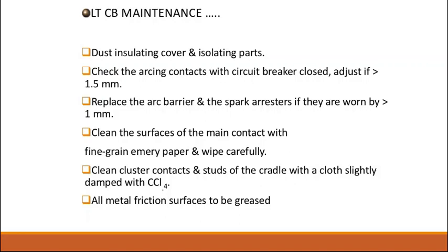What will happen during long periodical operations, there is carbon deposited on the contact. The carbon will offer some resistance. So as I told, the contact resistance, if the carbon deposition is more, the contact resistance is more. If the contact resistance is more, the voltage drop will increase.